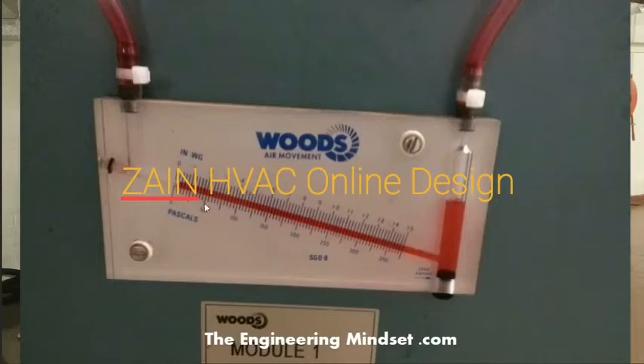A really good tip is to mark these, so put a sticker or draw a pen mark to display where a clean filter reading should be and where a dirty filter reading should be. That way, when your maintenance team does the walk rounds, you can go along, and if it was at 150 pascals and has gone up to 200, the red dye, then you'll know that you should have changed the panel or the filters by now, and you can get the maintenance regime in place to do that.